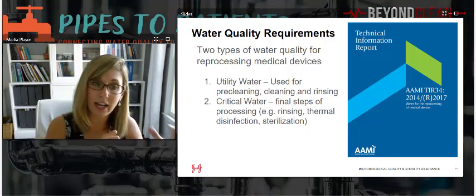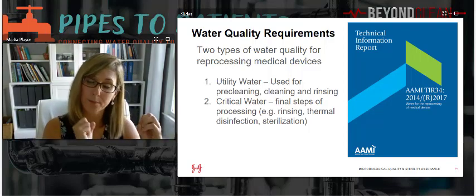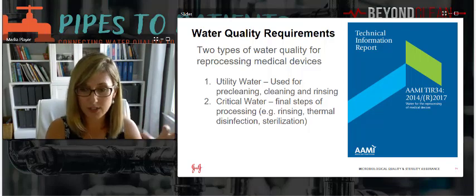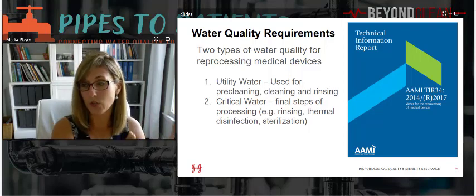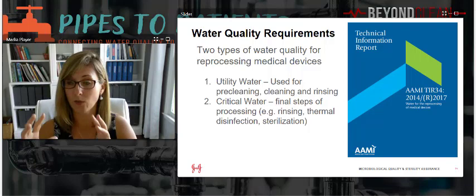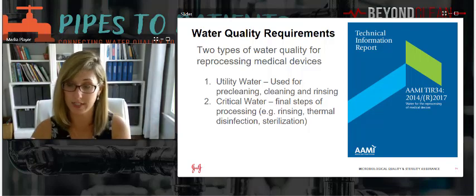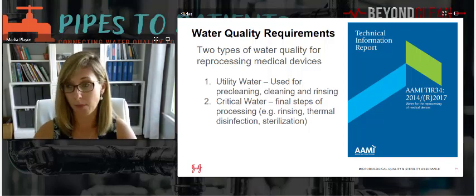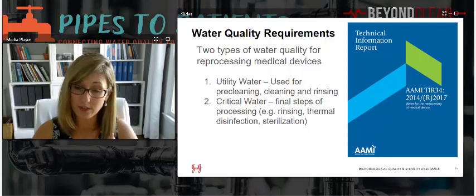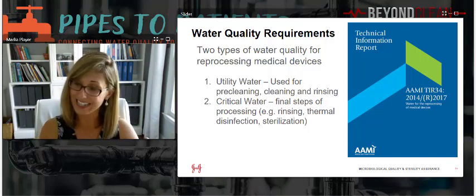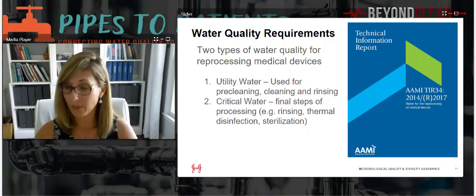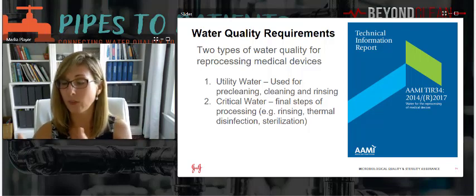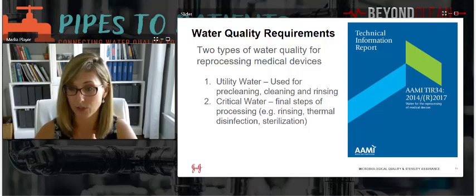It's defined not only on the performance qualification piece that engineering might do, but also very well defined on what would be required by sterile processing personnel in the routine monitoring of water quality. It gives clear instructions on what testing to do, what the acceptance criteria is, and what to do if you're not meeting the acceptance criteria.